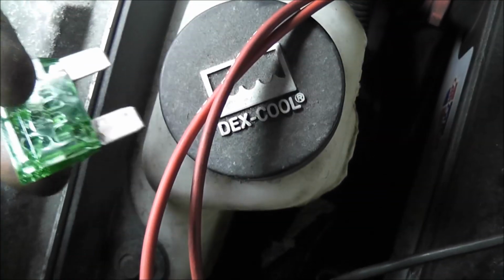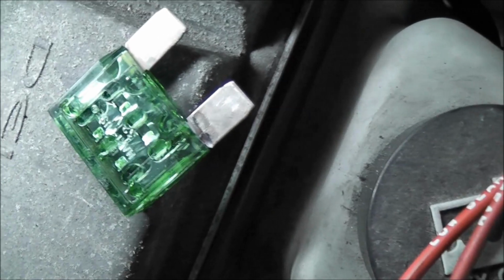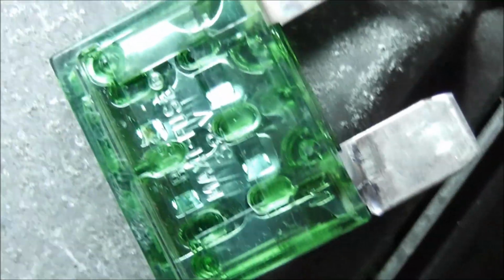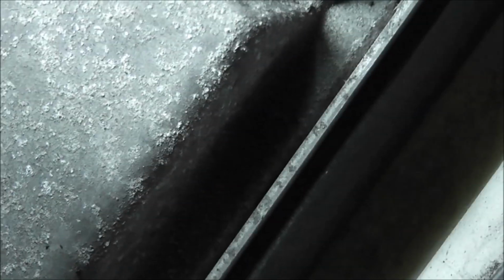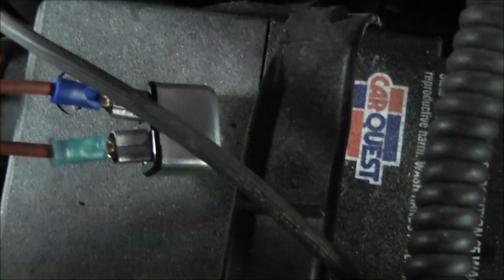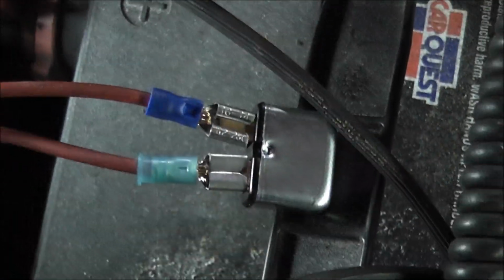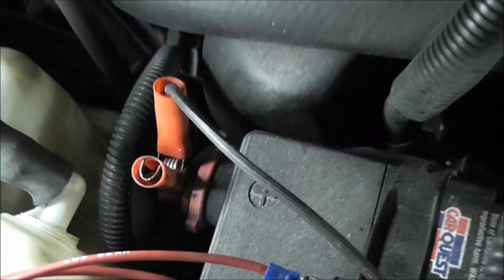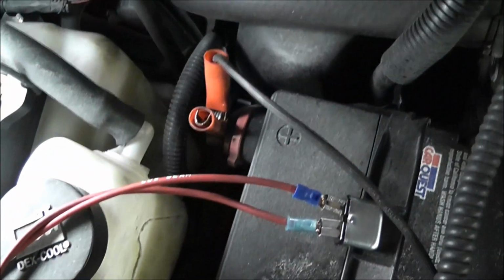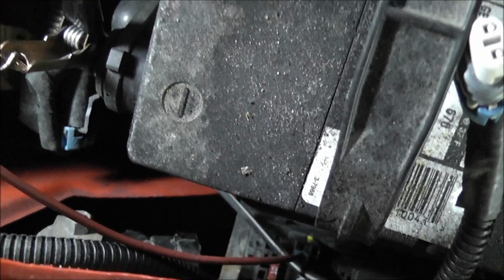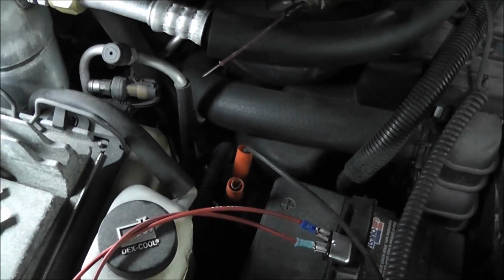Alright, pulled the fuse out. I don't know if you're going to be able to see it, but down in the center between the two terminals, it's blown. What we did is we made a jumper wire setup, and I got a 30 amp circuit breaker, so we're going to turn it on, see if we hear the pump run. I turned it on and the pump runs. So it may just be that simple.